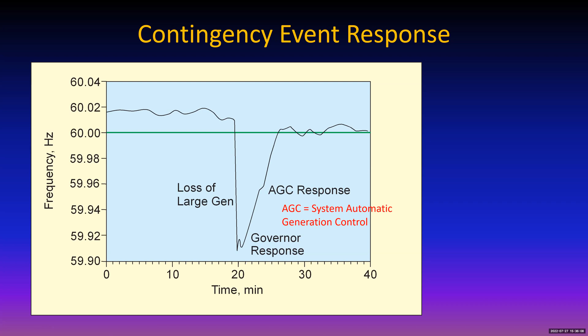This is the kind of curve you're looking at, and this is a trigger - the instrumentation is looking at that frequency, and if it sees a big spike like that, everything else on the system knows exactly what it needs to do, just like a hockey team when the puck goes down to the other end of the ice. So AGC is automatic generation control, meaning turning on that generator when you need it.